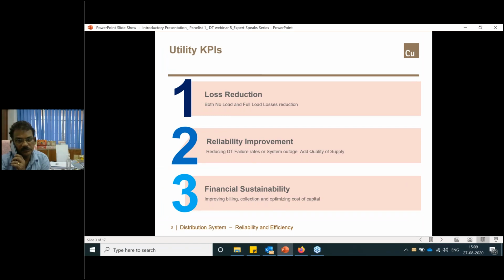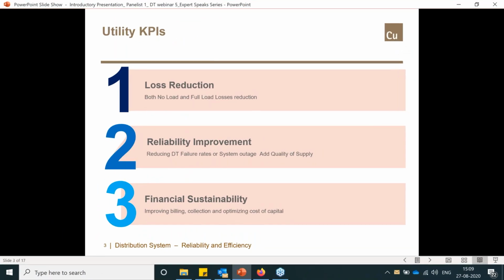Around 12 million distribution transformer today in India's electricity supply, and almost 10% of that fail every year, resulting almost 5,000 to 6,000 crore loss to Indian exchequer. That's a financial loss, and that becomes a big polluter. And high failure rate. When I say high failure rate, some of this failure can get into the catastrophe, which is breaching the electrical safety. There are challenging current practices onto the one-day breakdown, repair, replacement, as well as procurement. So when we have challenging current practices, we have to have an approach like fit and forget solution.